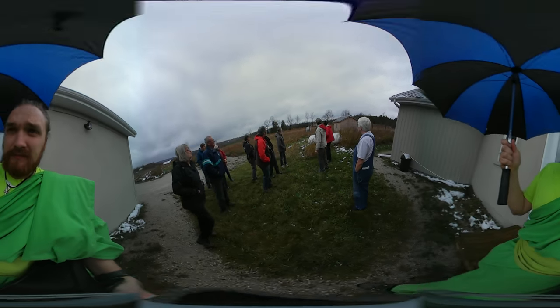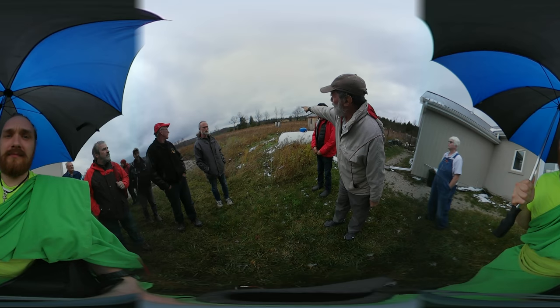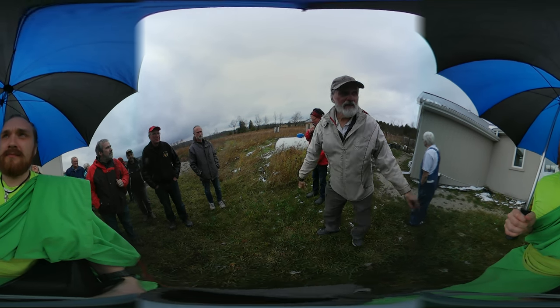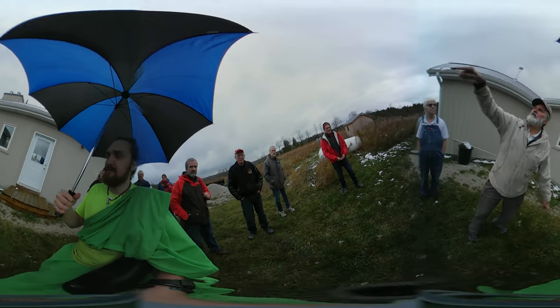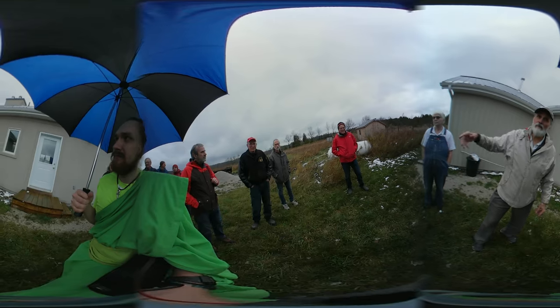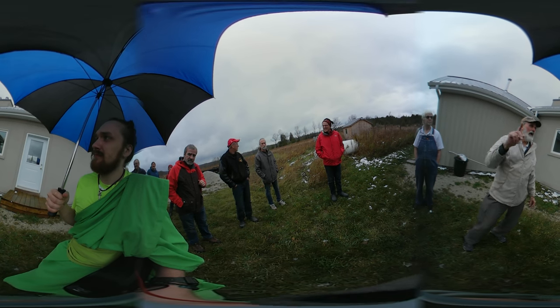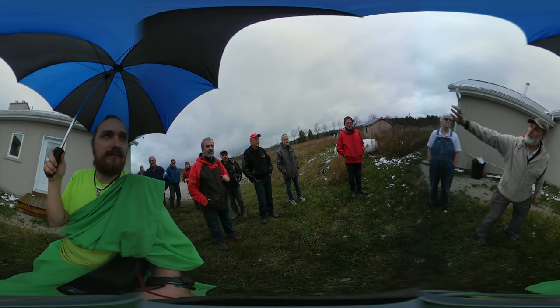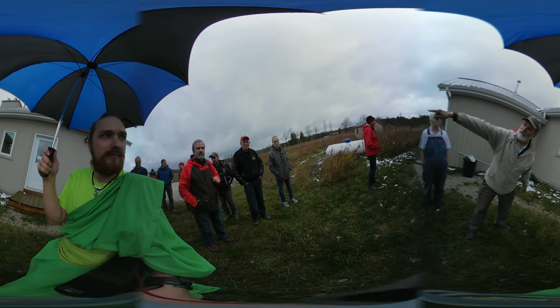Okay, so you can see, it's 119 or 120 feet. There should be at least 125 feet of air, because whether that air comes into those tubes at minus 25 or plus 30 degrees Celsius, by the time it gets in here, it's at the temperature of the ground. Someone asked what happens if I did a snake type. You need less space, and maybe it could be used for someone who doesn't have the footage that I have, but by causing all those turns, you have a greater risk of condensation. So by only having the one bend, and remember that it's much lower at that end than at this end.